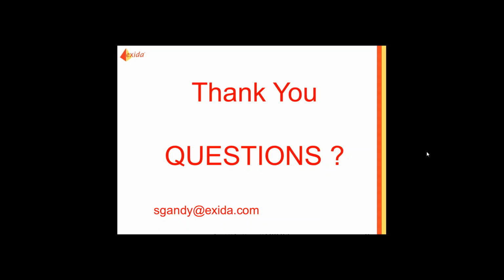Here's another question. What does it say here? If a proof test in the SRS says 1 year, but the designer needs to increase to 6 months to achieve the required SIL to improve PFD, is this okay? Well, yeah, but you should ask why. I mean, that's one way of doing it, but obviously the equipment he selected isn't as good as what could be specified. But yes, that's one way to do it.